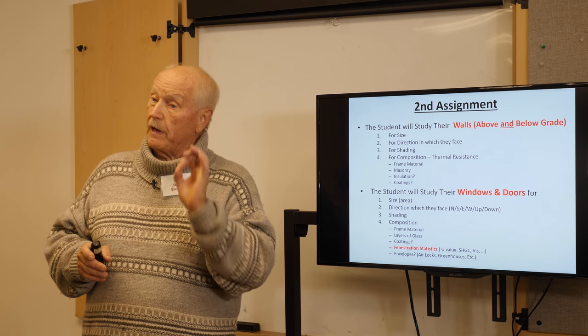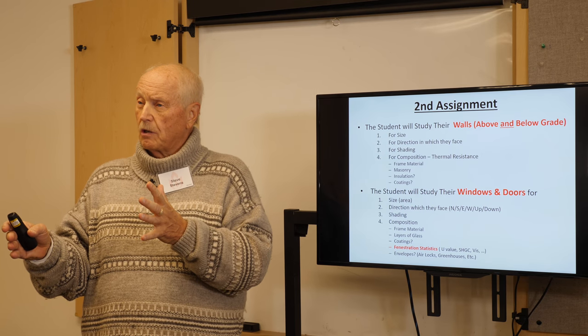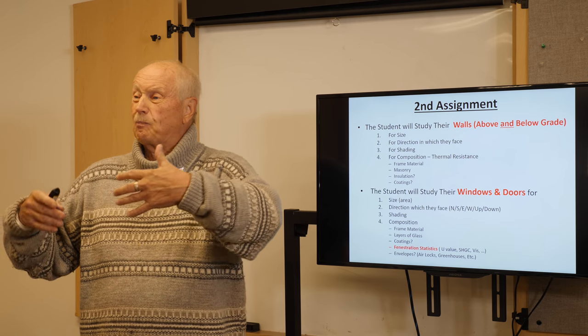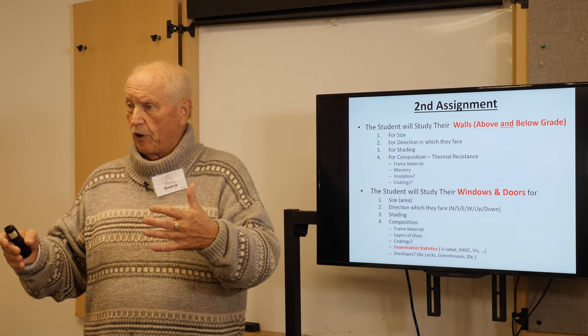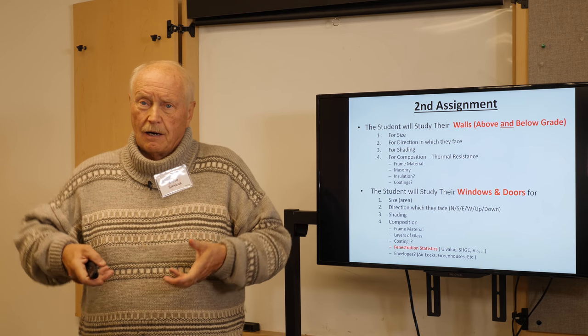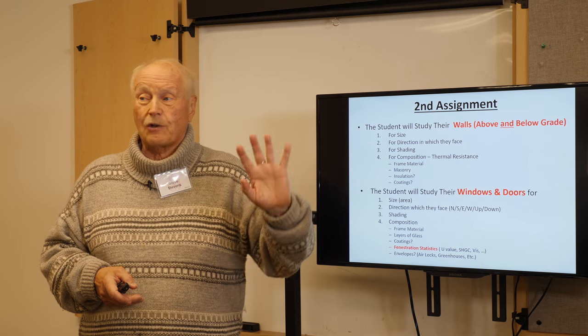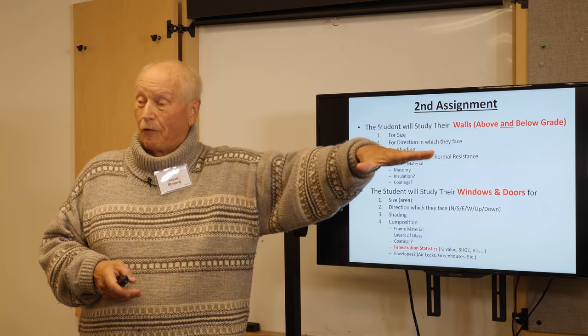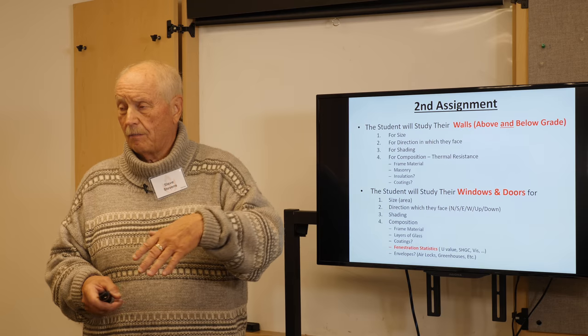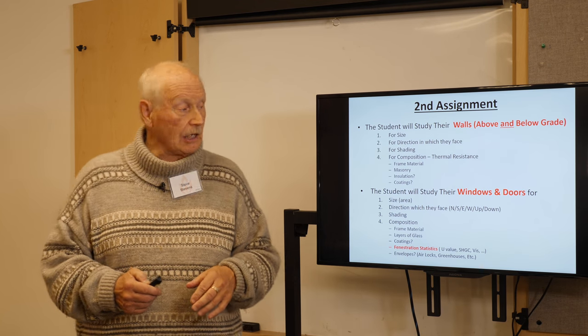Outside of the basement wall is better than inside of the basement wall, because then that basement wall is a great thermal mass. And that thermal mass will retain its ballast. It's just amazing ballast for you. So thinking, if you've got the energy, you dig around and you put in 4 inches of polyiso, that's about R28, for 4 foot down, and you're digging and tossing aside and then putting it back. That will do amazing things for the whole house by doing the basement.